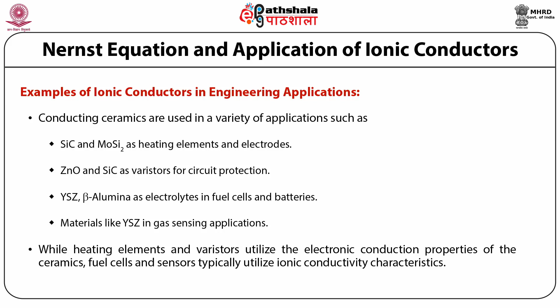Varistor or voltage dependent resistors. Varistors are devices offering high resistance at low voltages and low resistance at high voltages. These are used to protect a circuit against sudden upsurges in the voltage or transients, which you can see in this figure. The typically used materials are zinc oxide and silicon carbide powders bonded in a matrix with an intergranular layer that is highly resistive. The current voltage characteristics are governed by the electrical nature of grain and intergranular layers. The basic principle of operation is that the material resistance is high at low voltages and decreases when voltage is increased, allowing excess current to pass through, away from the protected circuit.